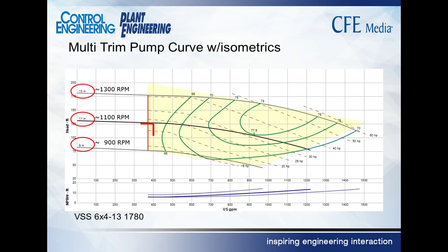Okay, with that understanding, here's a pump curve. A typical pump curve, we can see our 4 parameters on there. We have the flow on the horizontal axis. We have the head on the vertical axis on the upper part of the graph. In this particular one, the efficiency are the green isometric lines, and the brown dashed lines are isometric horsepower indications. So a little different presentation of the same information that we saw before.